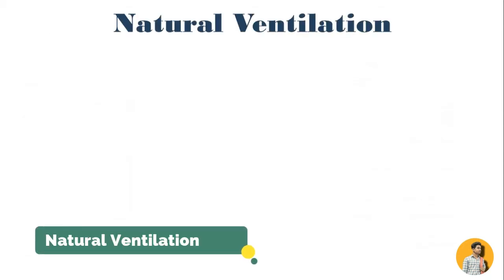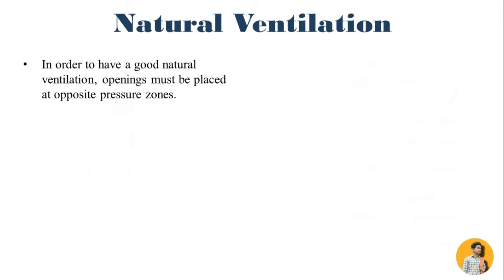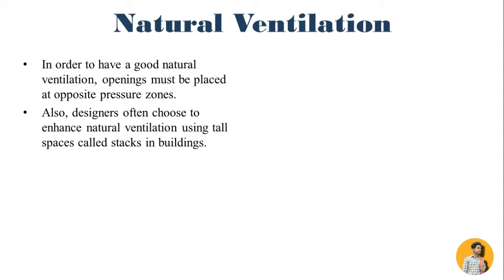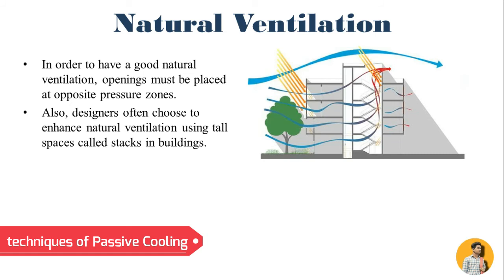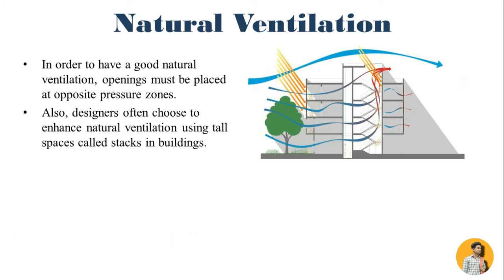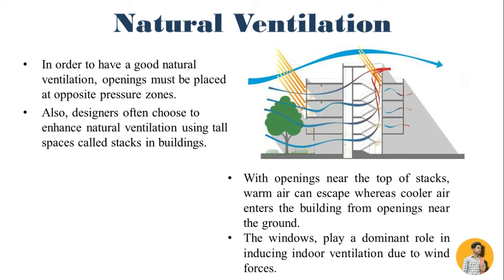The first technique is natural ventilation. In order to have good natural ventilation, openings must be placed at opposite pressure zones. Designers often choose to enhance natural ventilation using tall spaces called stacks in buildings. With openings near the top of stacks, warm air can escape whereas cooler air enters the building from the openings near the ground. Windows play a dominant role in inducing indoor ventilation due to wind forces.